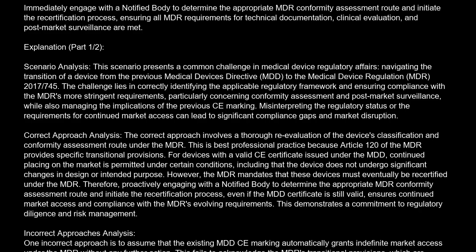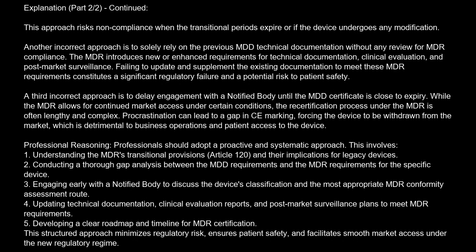This fails to acknowledge the MDR's transitional provisions, which are time-limited and require eventual conformity assessment under the MDR. This approach risks non-compliance when the transitional periods expire or if the device undergoes any modification. Another incorrect approach is to solely rely on the previous MDD technical documentation without any review for MDR compliance. The MDR introduces new or enhanced requirements for technical documentation, clinical evaluation, and post-market surveillance.